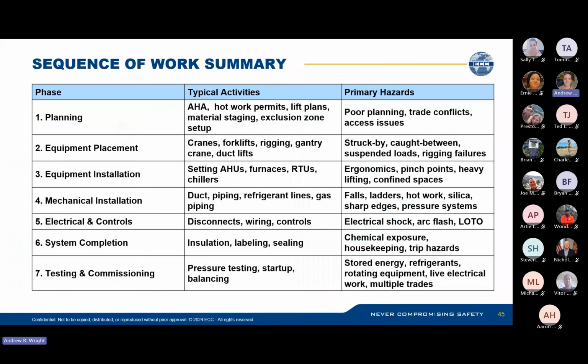Sequencing is really important. So a summary of a typical work sequence that I would do on an HVAC job is I'd plan it first: get the AHAs, the hot work permits, lift plans, material staging, exclusion zone set up, make sure that's all dialed in. Then equipment placement. When you're doing new construction, how is the equipment going to get installed? Are they going to use a crane, a forklift? Is there going to be rigging, gantry cranes, duct lifts, what have you? How is the equipment going to be installed once it's set?